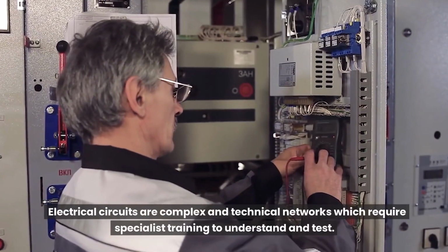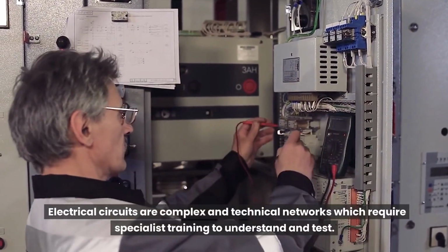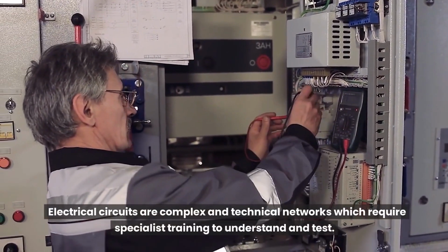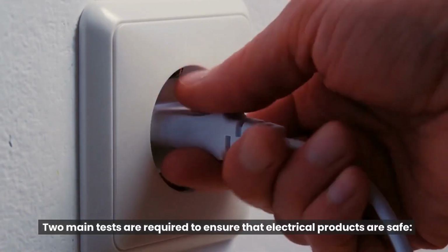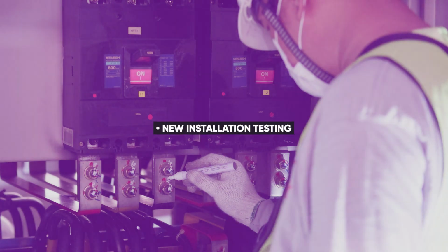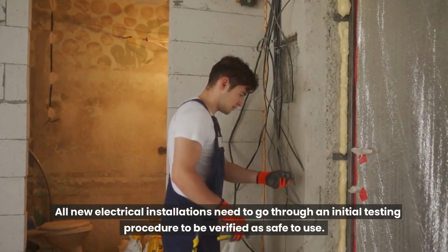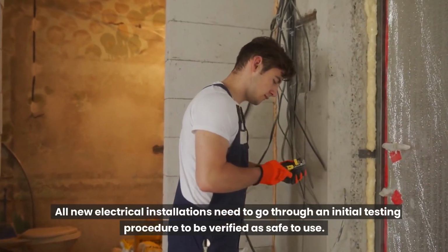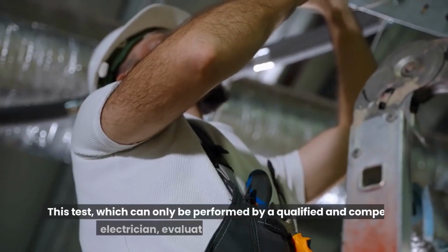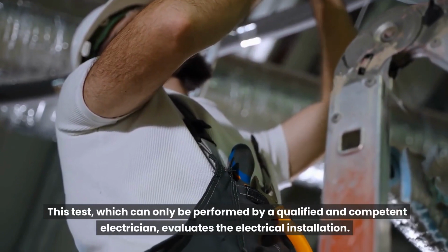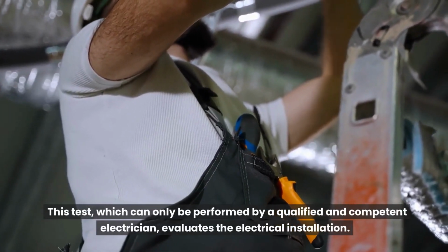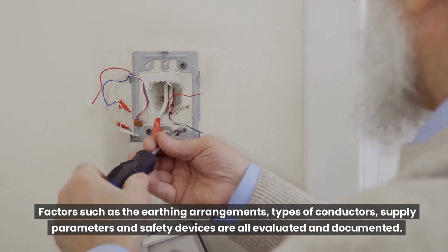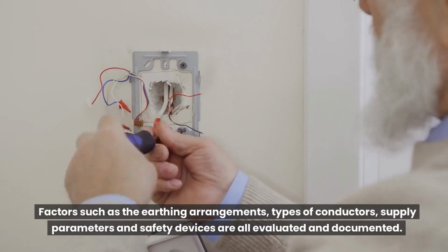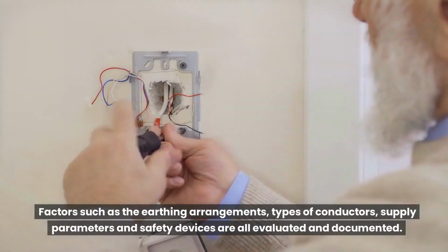Electrical circuits are complex and technical networks which require specialist training to understand and test. Two main tests are required to ensure that electrical products are safe. New installation testing. All new electrical installations need to go through an initial testing procedure to be verified as safe to use. This test, which can only be performed by a qualified and competent electrician, evaluates the electrical installation. Factors such as the earthing arrangements, types of conductors, supply parameters and safety devices are all evaluated and documented.